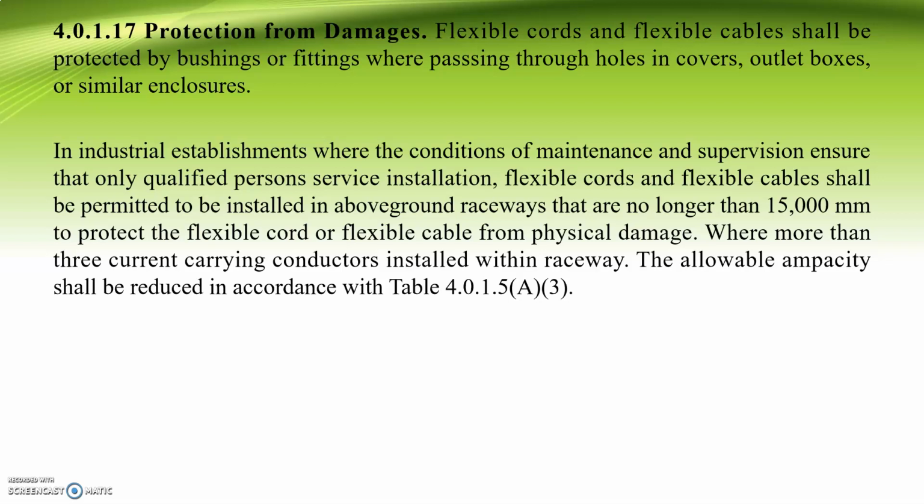In industrial establishments where the condition of maintenance and supervision ensures that only qualified persons service the installation, flexible cords and flexible cables shall be permitted to be installed in aboveground raceways that are no longer than 15,000 mm to protect the flexible cord or flexible cable from physical damage. Where more than 3 current-carrying conductors are installed within a raceway, the allowable ampacity shall be reduced in accordance with Table 4.0.1.5A3.